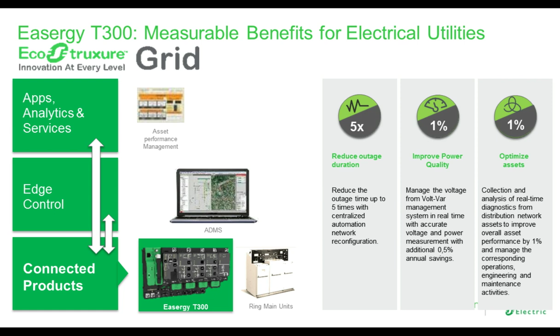Let's go back to the first benefit, associated with outage time reduction. In the public distribution application, the traditional medium voltage, low voltage substations are equipped with ring-main units with switch fuse solutions or circuit breakers for medium voltage, low voltage transformer protection, and manually operated load break switches for cable switching. When a fault occurs, a crew should be sent into the field in order to identify the location of the fault, possibly helped by checking the position of the fault passage indicator in different medium voltage, low voltage substations, if such devices are installed on the concerned feeder. This approach is time consuming and very costly and may lead to long outages.